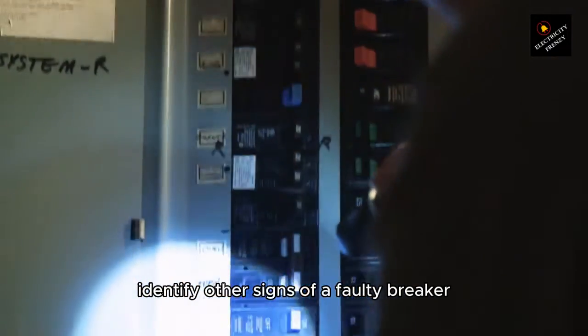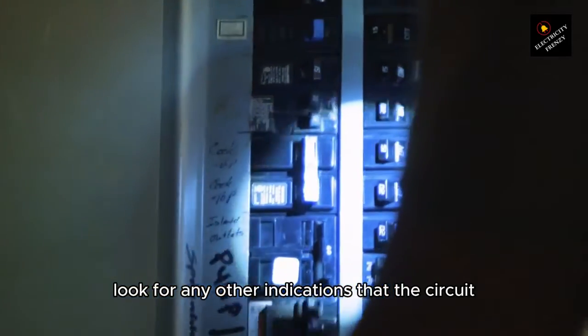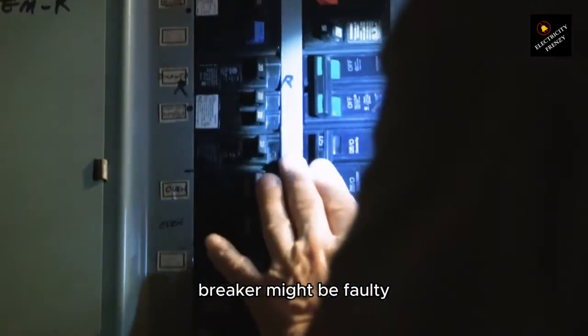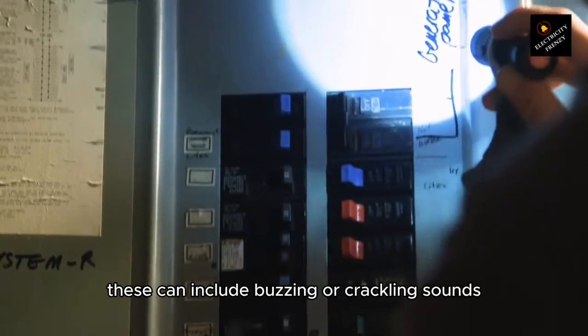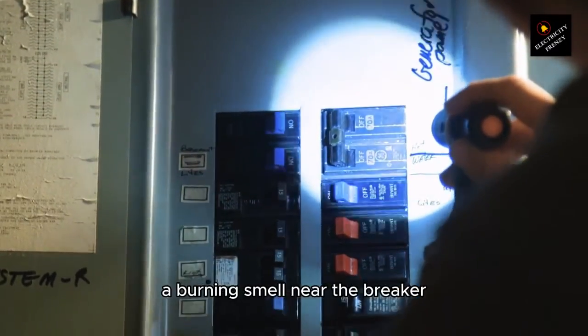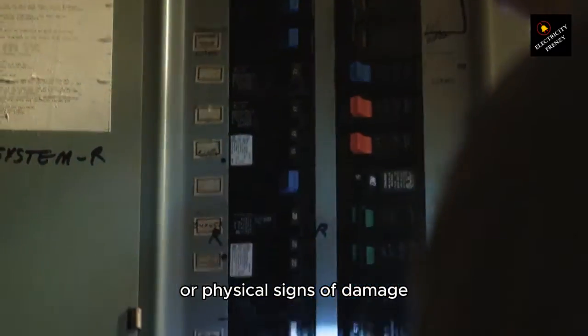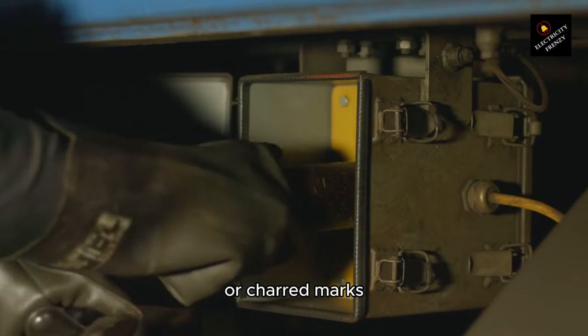Identify other signs of a faulty breaker. Look for any other indications that the circuit breaker might be faulty. These can include buzzing or crackling sounds coming from the breaker panel, a burning smell near the breaker, or physical signs of damage like a loose connection or charred marks.